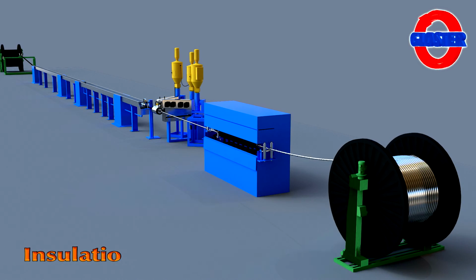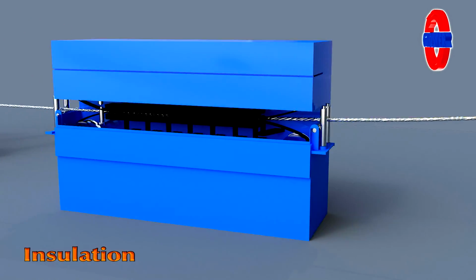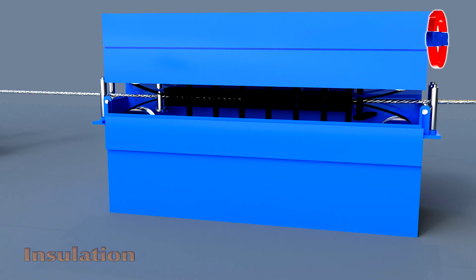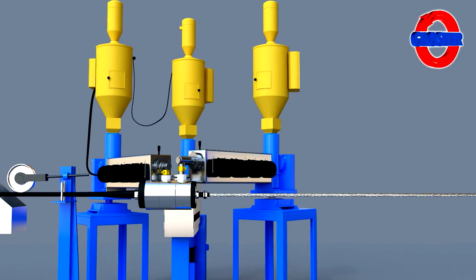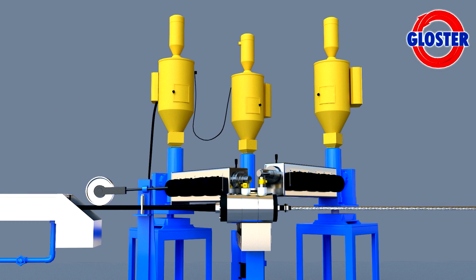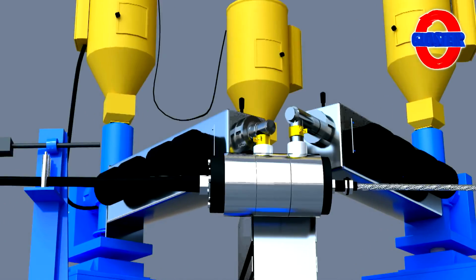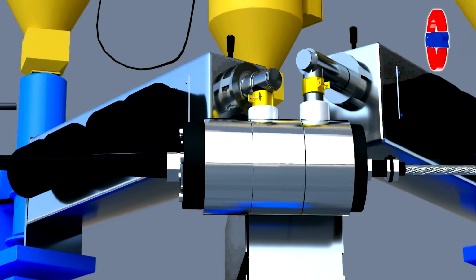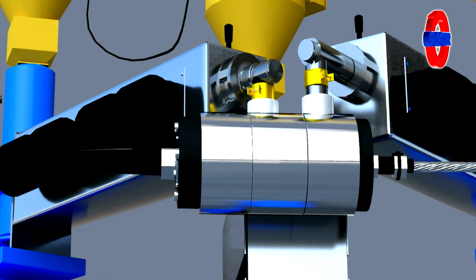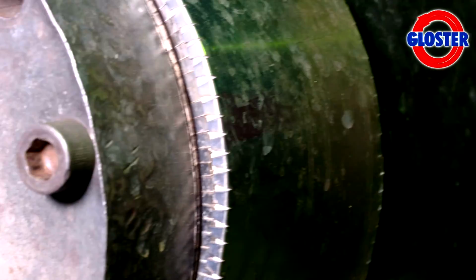For insulation, high-quality XLPE insulating compound of natural color is used on the conductor. It is chemically cross-linked by Silane process. The extrusion route with filtered air inlets and a positive air pressurized closed system ensures that the insulation process is completely free from any impurities and imperfections.